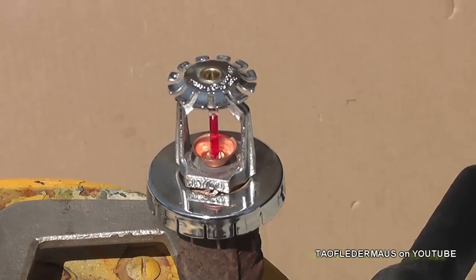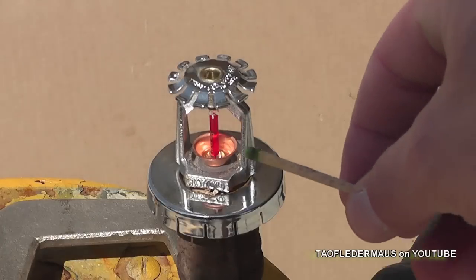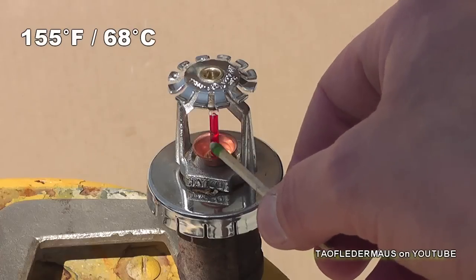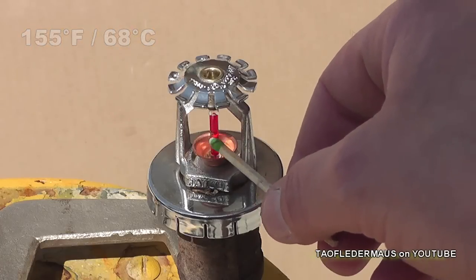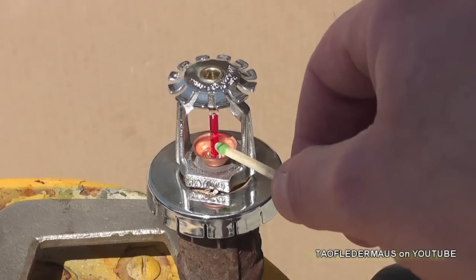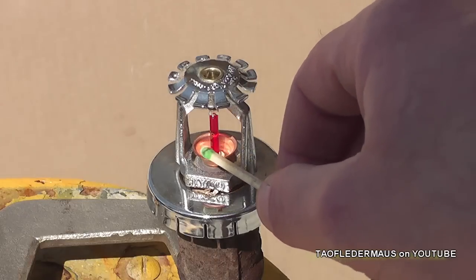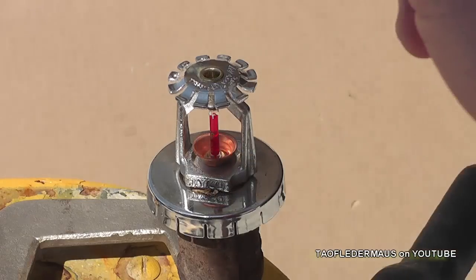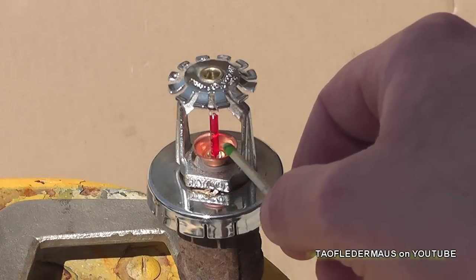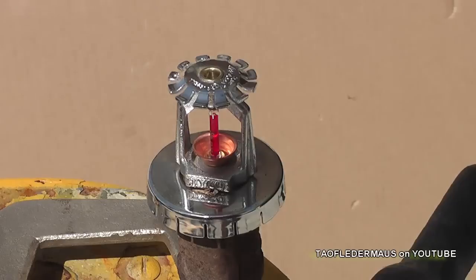This particular one works when it gets to 155 degrees. There's a liquid in here that will expand in this glass ampule and break it and release this plug, which is called a pip, and it's a one-time deal. You can't reset them, and once that is open, it sprays water out.